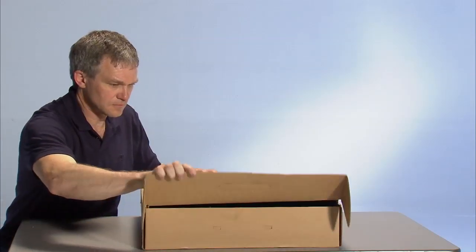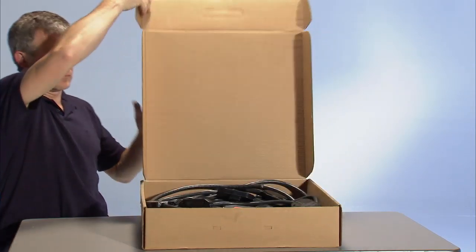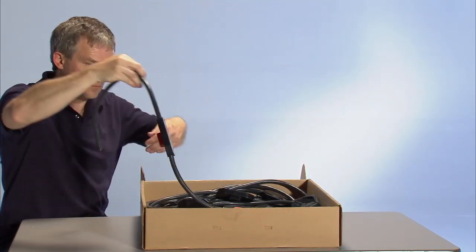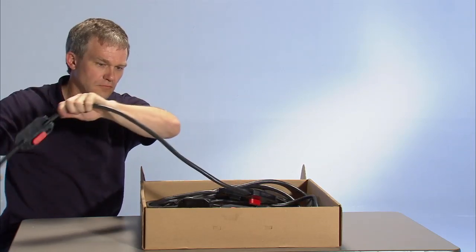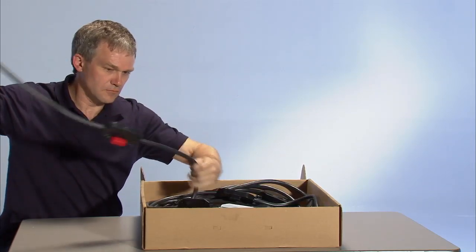The trunk cable is provided in a continuous spool. You decide how many drops you need to match the number of modules being installed and simply cut the cable to the length you need.